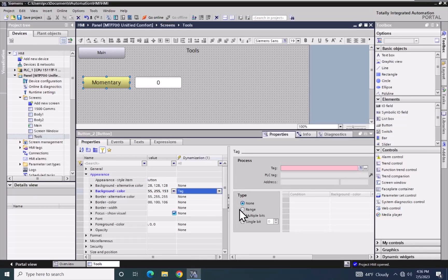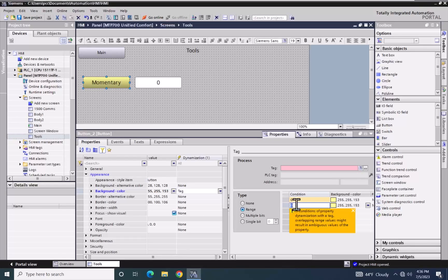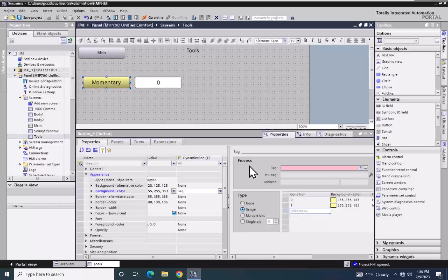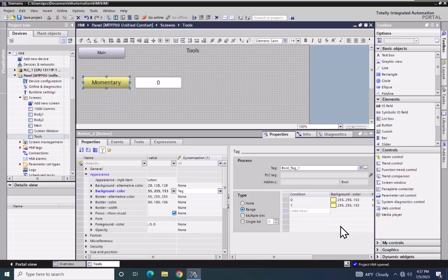For the type of animation I'm going to select range. In the range animation there's a condition that can be entered in, so I can put in a range of values or a single value. I'm going to put in two conditions: condition zero and condition one. Next I will select the tag value and go to my HMI tags and pick my tag table and pick my bool tag underscore one. This tag will be used to determine which condition is going to be used.